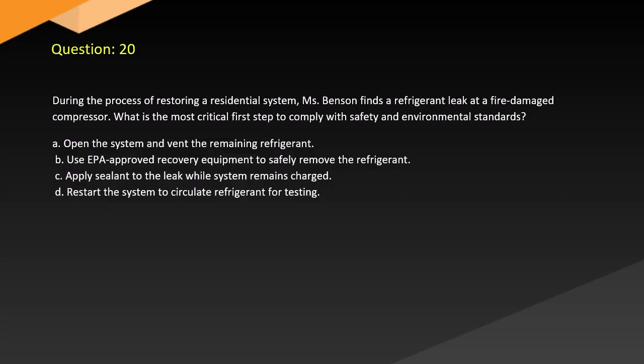Question 20. During the process of restoring a residential system, Benson finds a refrigerant leak at a fire-damaged compressor. What is the most critical first step to comply with safety and environmental standards? A. Open the system and vent the remaining refrigerant. B. Use EPA-approved recovery equipment to safely remove the refrigerant. C. Apply sealant to the leak while the system remains charged. D. Restart the system to circulate refrigerant for testing.